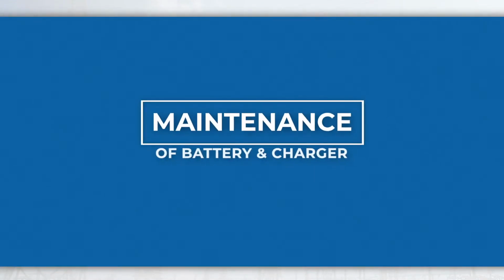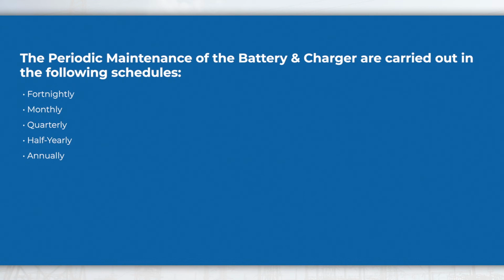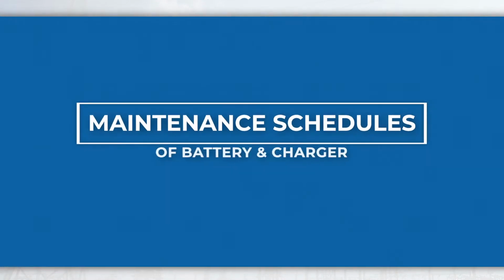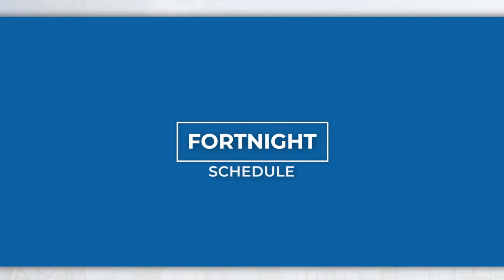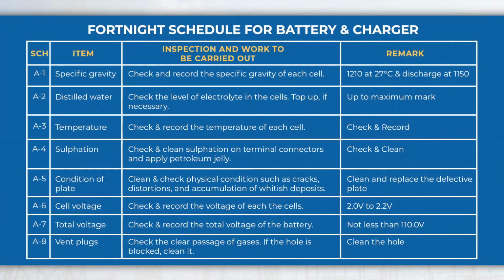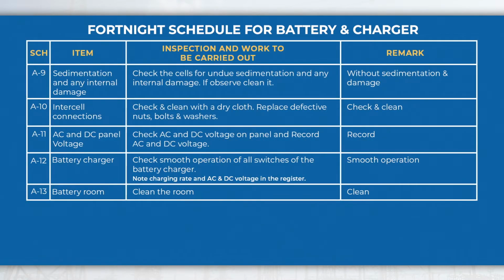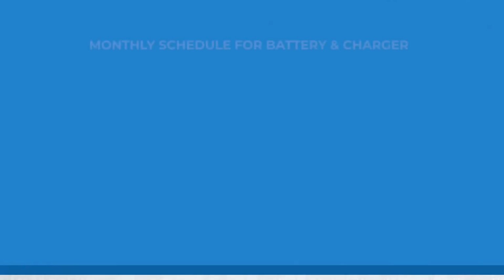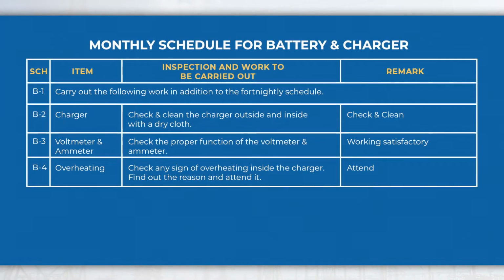Maintenance of battery and charger. The periodic maintenance of the battery and charger is carried out in the following schedules. Maintenance schedules of battery and battery charger. Fortnightly schedule: perform activities like checking specific gravity, level of electrolyte, temperature and voltage of cell and total voltage of battery, and check AC and DC voltage on panel, etc. Monthly schedule: perform activities like checking proper function of the voltmeter and ammeter and any sign of overheating inside the charger, etc., in addition to fortnightly schedule activities.